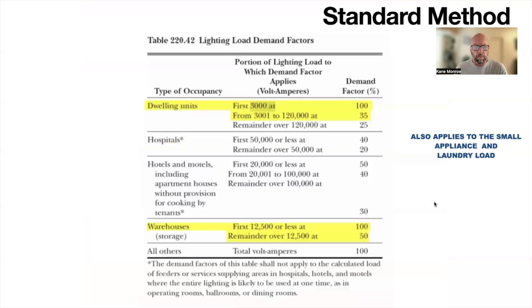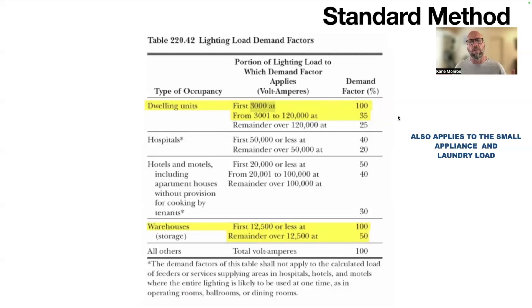Looking at Table 220.42, you'll see a demand factor we have to apply. For the first 3,000 VA we apply 100 percent. After that, from 3,001 to 120,000 VA, we apply a 35 percent demand factor — that's a multiplier. What this is telling you is that for a large house, they're betting you won't be using all the electric appliances and receptacles at once, so they knock it down and apply only 35 percent on that portion.